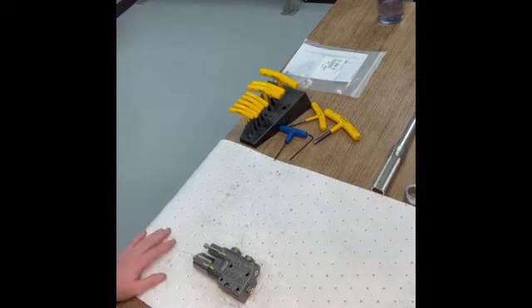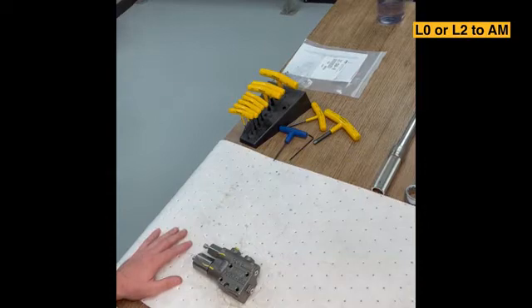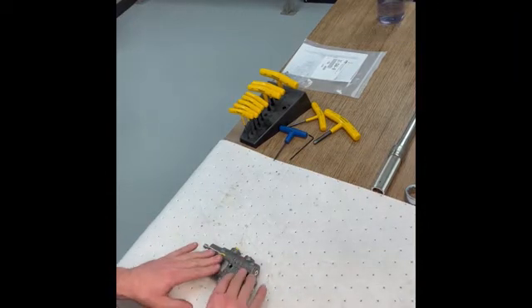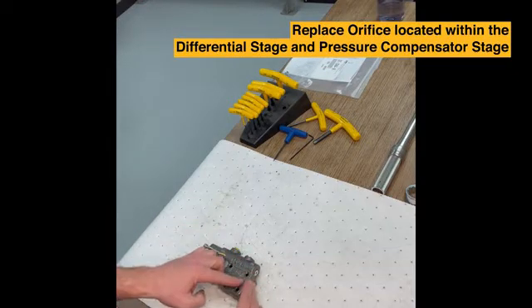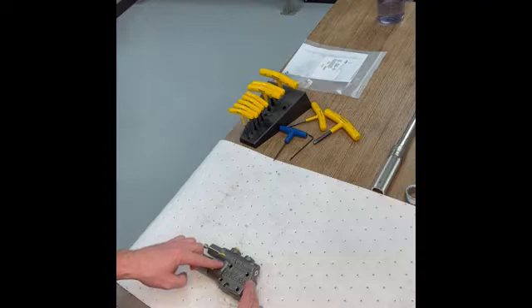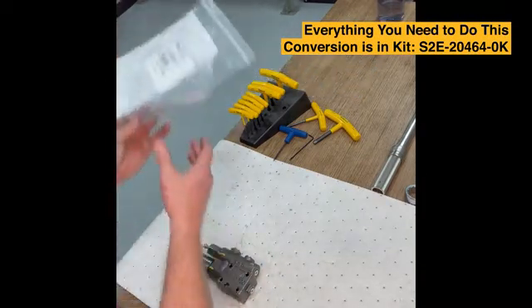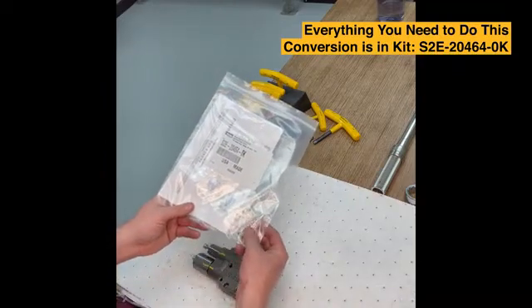Next I'm going to show you how to convert your L0 or L2 control to an AM. If you're starting with an L2 control like I am here, you're going to need to replace the orifice that's located between the differential stage and the pressure compensator stage with a plug. Everything you need to do this conversion is included in kit number S2E20464-0K.